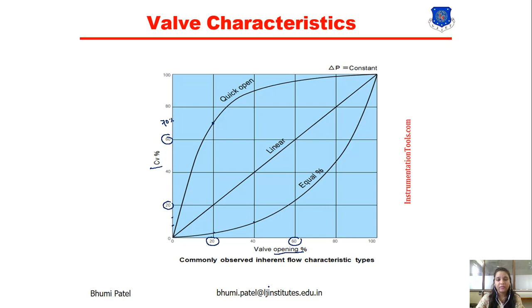Now the first characteristic is quick opening. Now what is the quick opening? Inherent flow characteristic with high flow at initial percentage of travel. That means in the quick opening valve, the plug produces a large increase in flow for a small initial change in the stem position. So near the maximum flow, it is reached at a relatively low percentage of maximum stem lift.